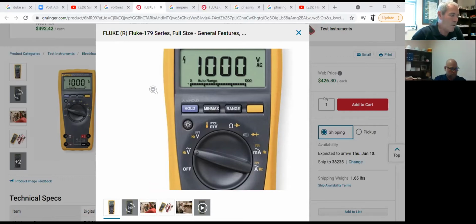What do you think would happen if I was actually checking AC voltage at 480 volts and I had it in the DC position? Would it blow the meter up? I don't think it would blow it up, but I don't think it would read anything. It's not going to read correctly as long as you don't go over the rating of the meter. The new ones now, they're going to throw up an error that says ERR. Any of the wrong readings for what you're trying to apply it to, it's just going to give you that and let you know you're not in the right position with your knob.